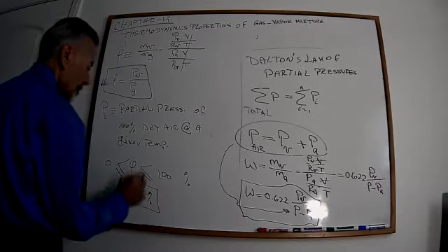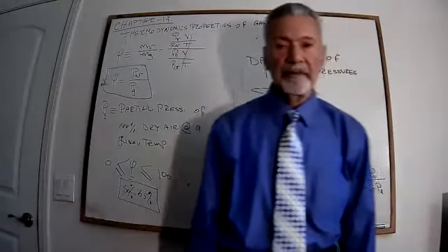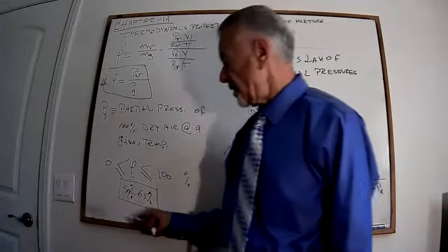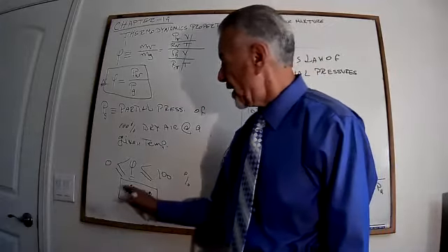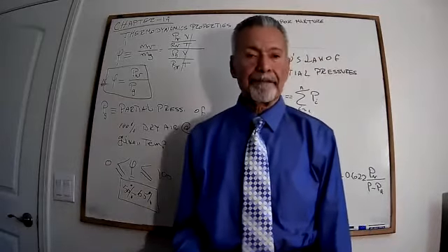This is something that we can be comfortable with. 60% would be ideal, but it's hard to get an ideal. We can do it with air conditioning, but outside temperature or outside air, we have no control of it. So ideally, we want to stay within 50 to 65% relative humidity.